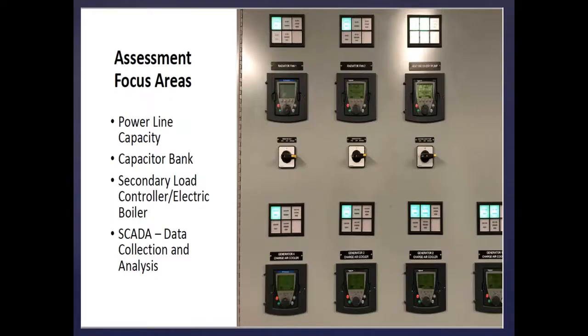Our task force and these studies have been completed, with modeling done on our power line, our failed capacitor bank in the plant, and our current boiler controls and SCADA. We now have a plan to deal with the reactive power problems that currently require us to operate our gensets in pairs. By increasing the voltage, we can basically go to one diesel operation, which is great bang for our buck. But to get there, we have to do some significant infrastructure enhancements.